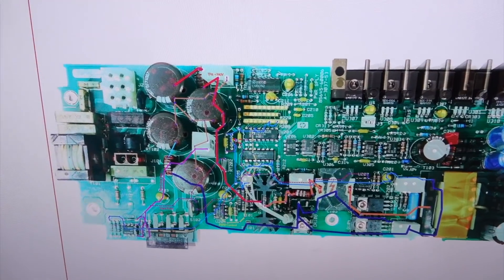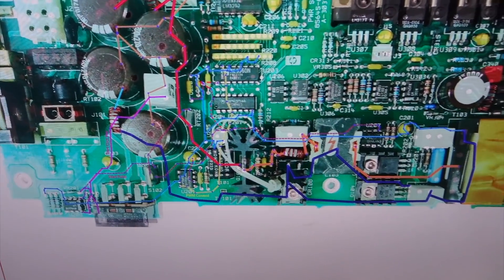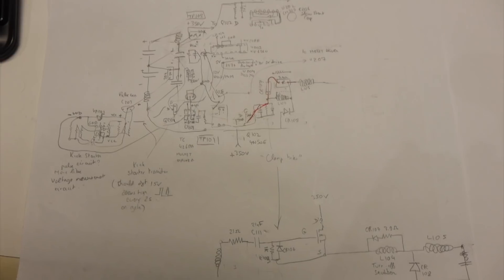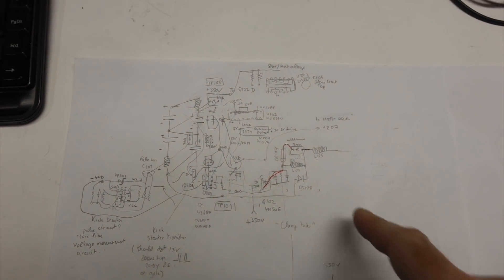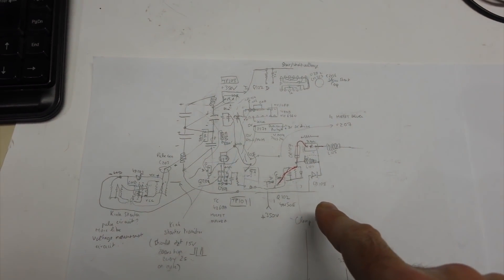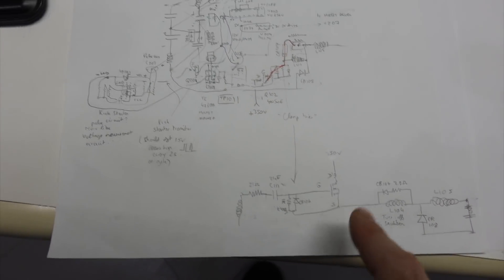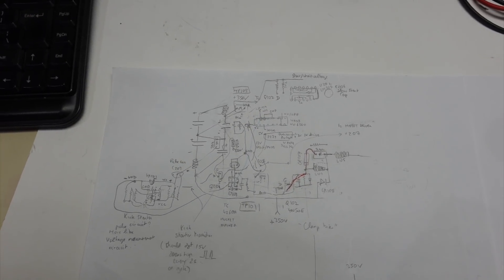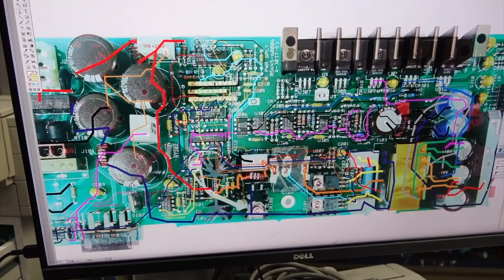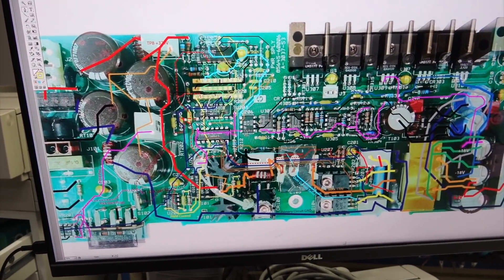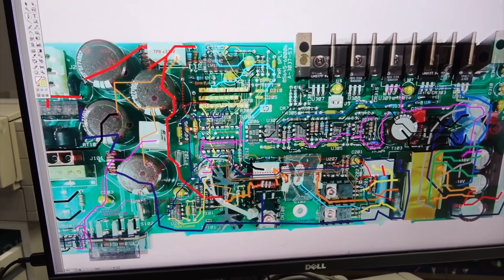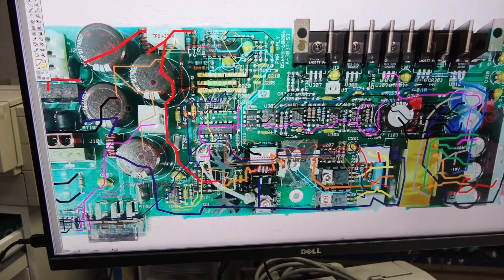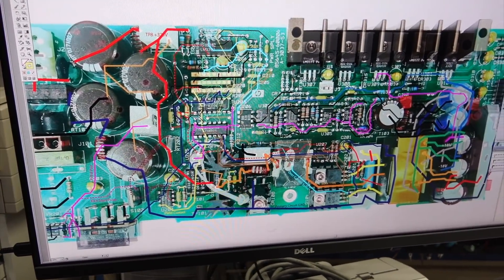And off you go, you start tracing. I do it both on the computer and also on a pencil schematic, so I can both do the wiring and also figure out what the schematics are at the same time. Here we go, it's all traced out. It actually took over a day to do this, a day and a half.